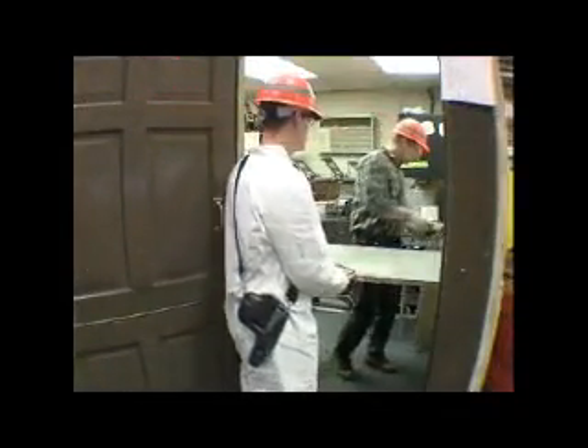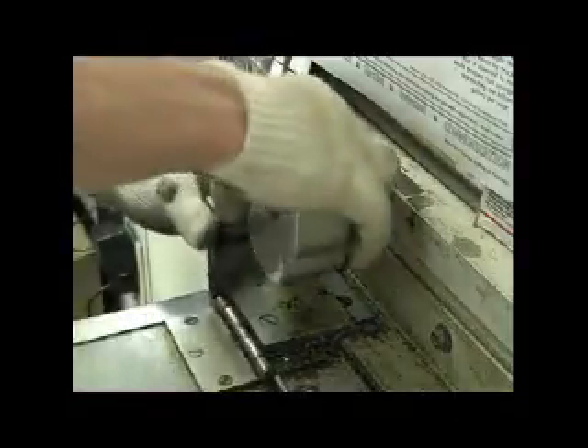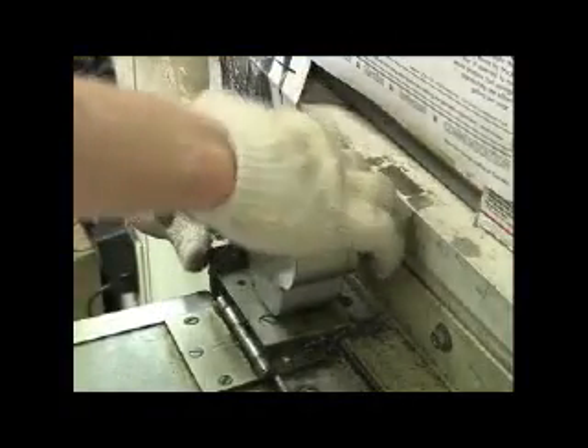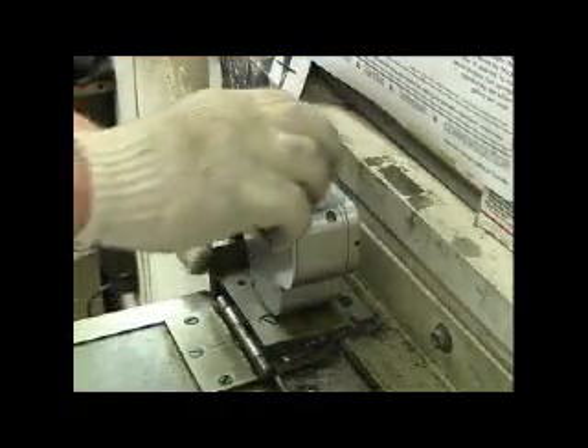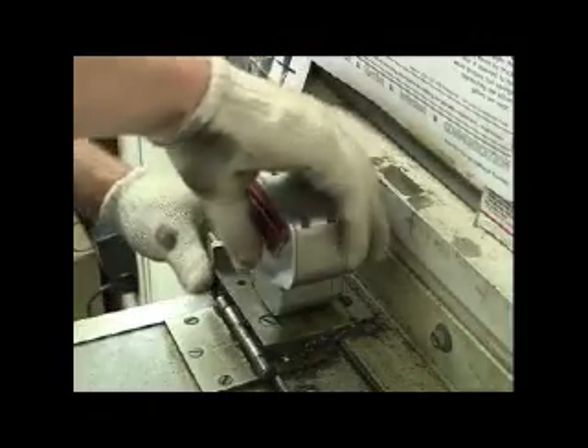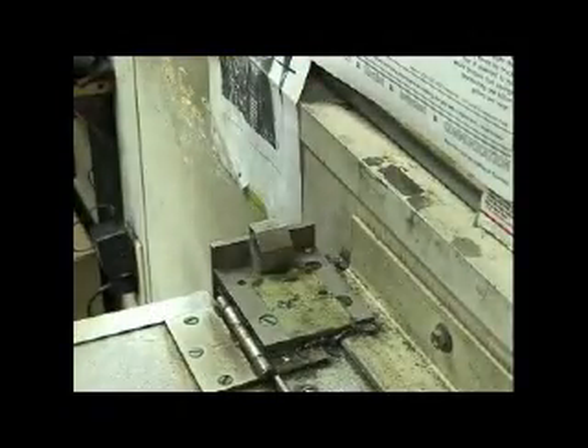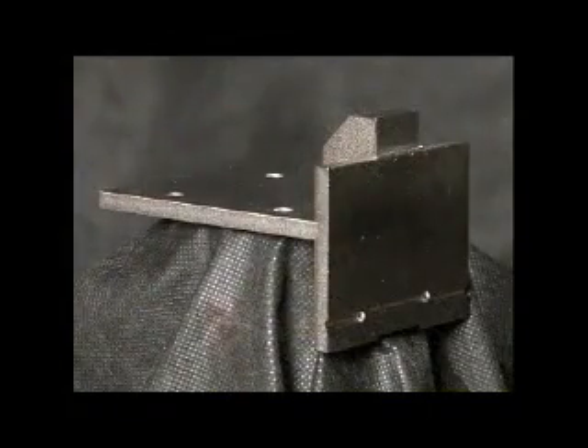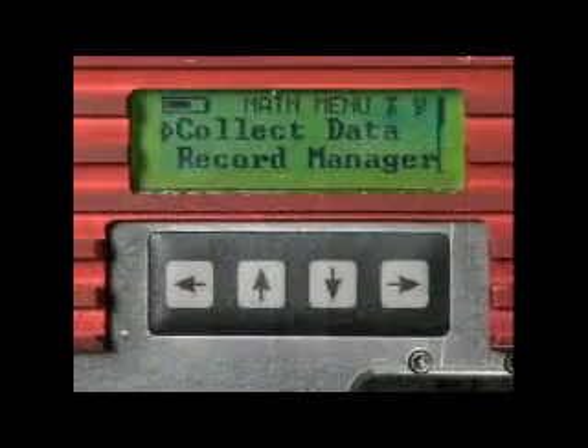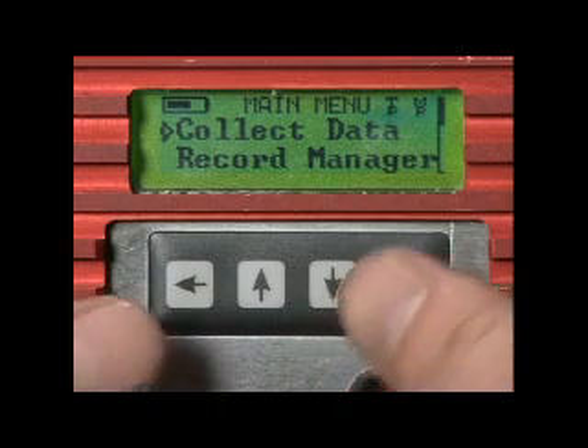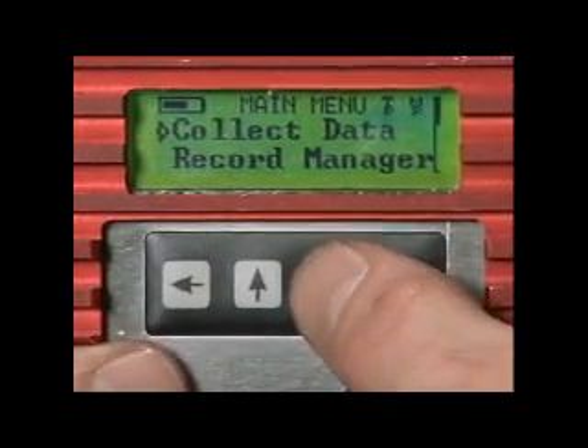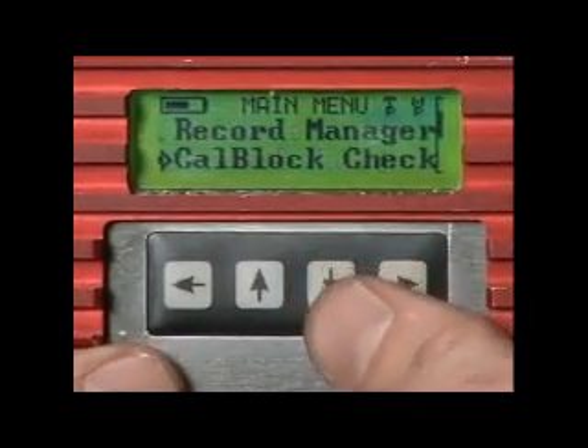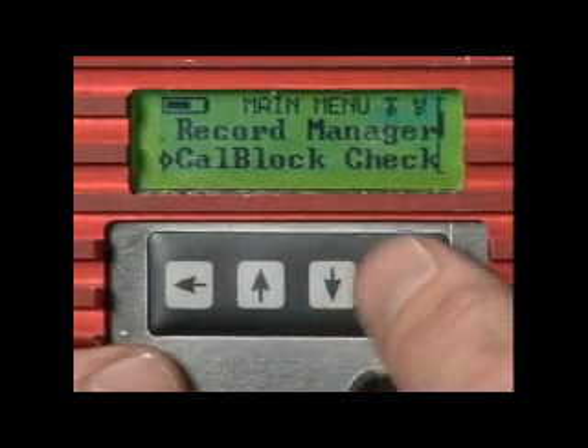Calibration. IEM recommends that you perform a calibration check on the Mini EWG both before and after each shift. A specially designed tool called a calibration block or CalBlock is provided with each gauge for this purpose. To check the gauge's calibration, turn the Mini EWG on and then scroll down the main menu to highlight CalBlock Check. Press the forward button.